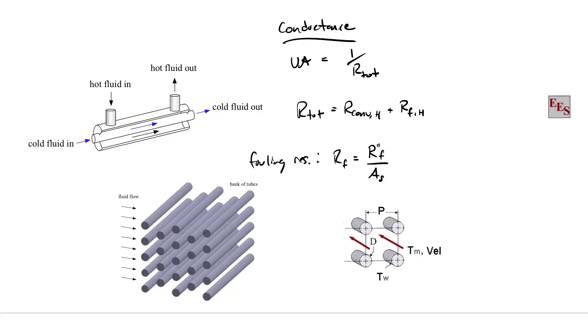That's a fouling resistance that I can then use in my equation here to calculate my one side fouling resistance. So here we have to add in the fouling resistance R F on the hot side. And then I have to conduct energy across our conduction across the wall. And then on the other side, I might also have the fouling resistance R F on the cold side. And then I have our convection on the cold side as well. So when I'm calculating my total resistance from one fluid to the other, I have one, two, three, five resistances in series that I have to account for.